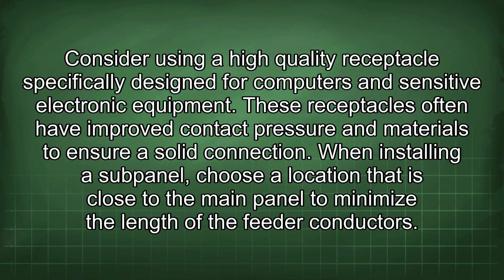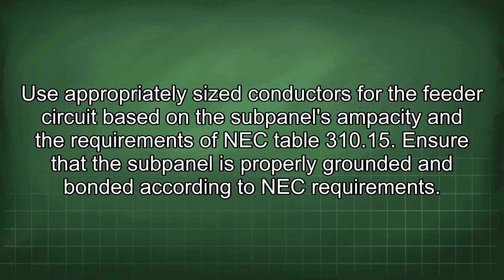When installing a subpanel, choose a location that is close to the main panel to minimize the length of the feeder conductors. Use appropriately sized conductors for the feeder circuit based on the subpanel's ampacity and the requirements of NEC Table 310.15. Ensure that the subpanel is properly grounded and bonded according to NEC requirements.